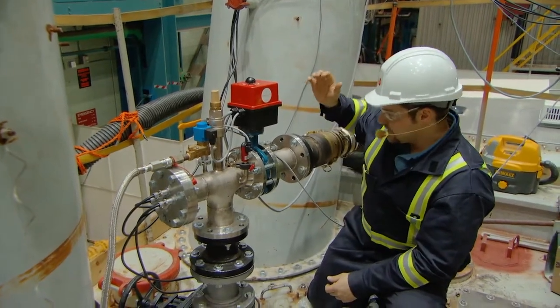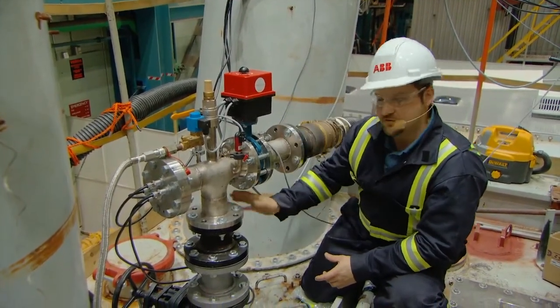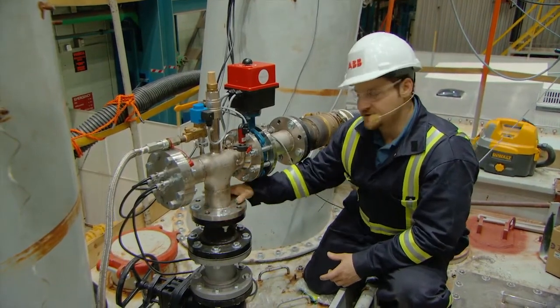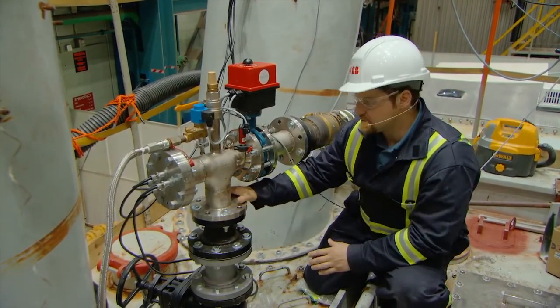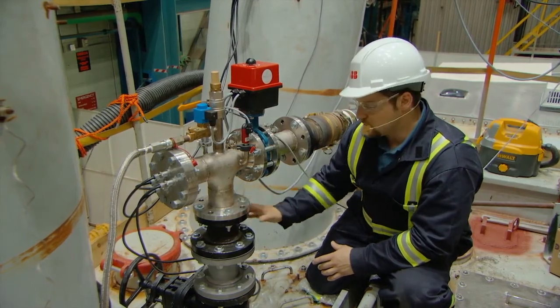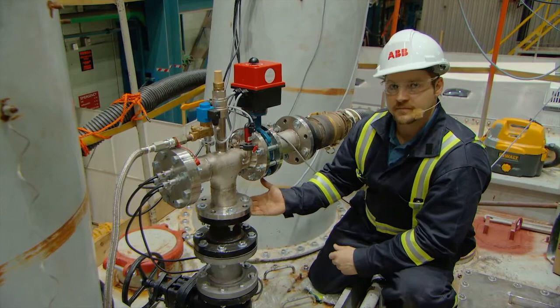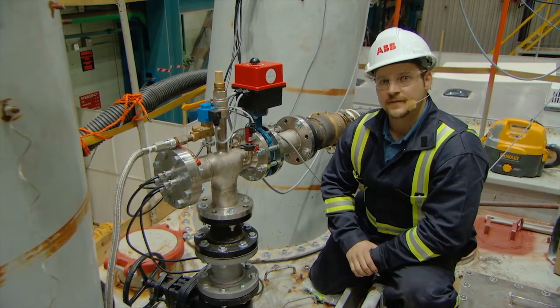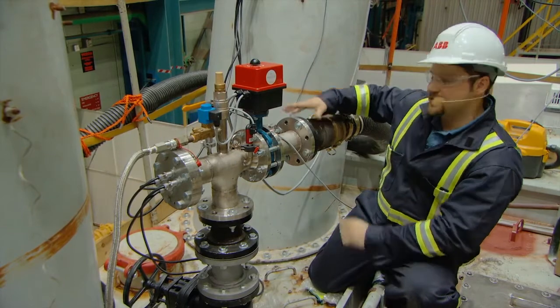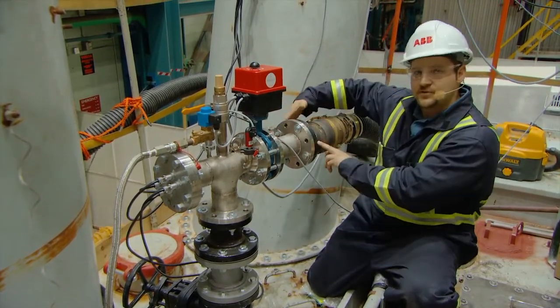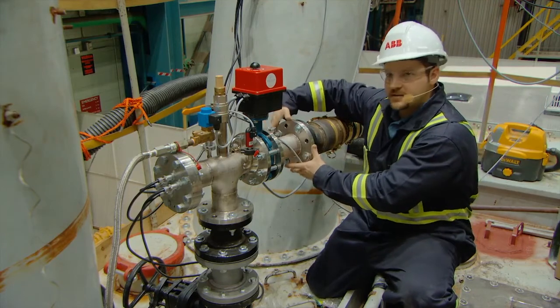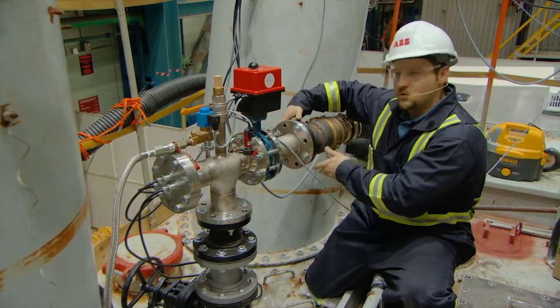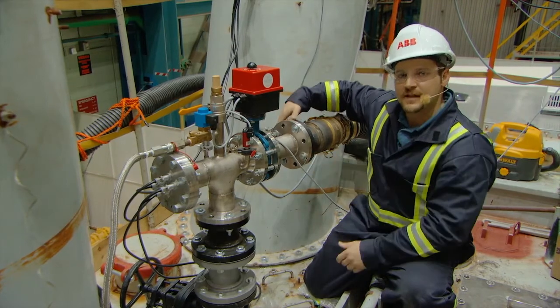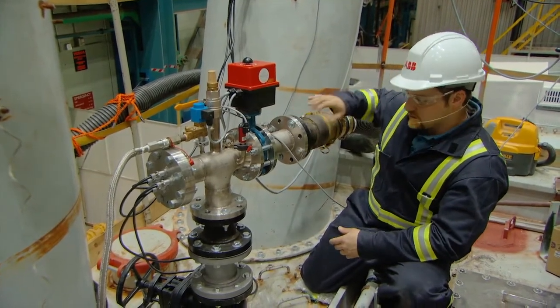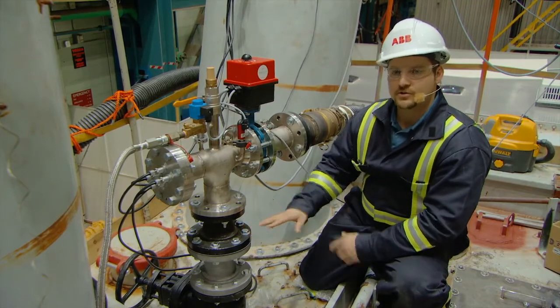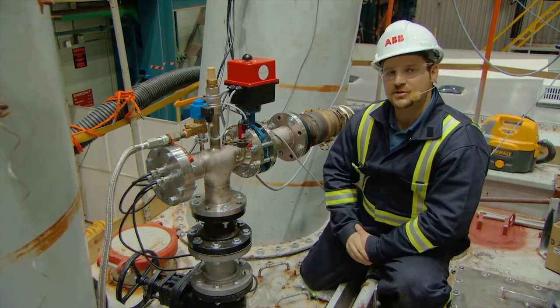The other important thing in regards to this valve is the adapter flanges. Since these flanges are not our standard type of flange, you do need an adapter that goes from this style of bolt pattern to our standard bolt pattern. I think that's about it. Oh yeah, this is the same thing right here. This flange as well is an adapter flange, which goes from the European style of standard flange to one of our Canadian or American style of flanges. Very important to have these adapters here and here in order to install the valve assembly onto the transformer.